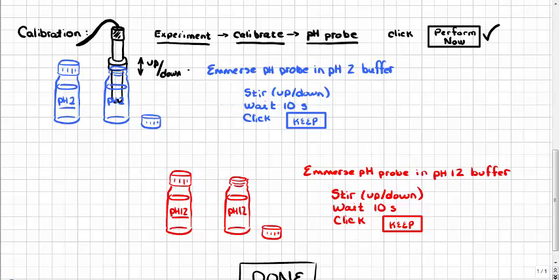Another thing to mention is that the large pH display that you'll see in the background will not be active during the calibration process. So don't expect to see any changes to that large pH display as you are doing the calibration. That large display will become active again when you finally complete the calibration. Okay, so when you've waited about 10 seconds or so and things seem to have settled down, the next thing that you do is click Keep. And this will tell the computer to memorize that particular pH 2 buffer response.